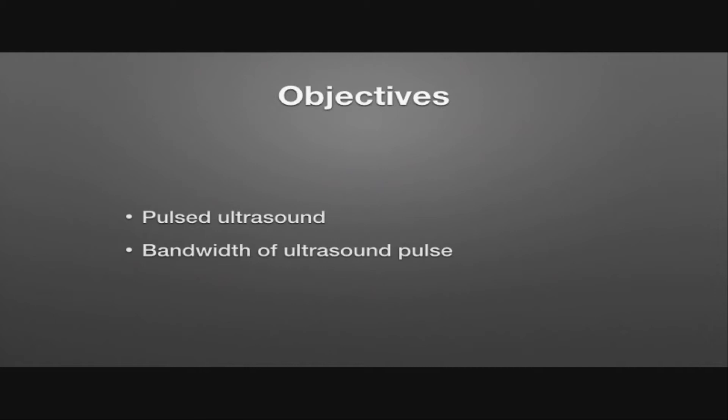Ultrasound images are actually made up from short pulses of transmitted ultrasound. The ultrasound machine will send out a short pulse and then listen for the returning echo. As well as talking about these pulses, we'll talk about the bandwidth, or the range of frequencies that are contained within the ultrasound pulses.